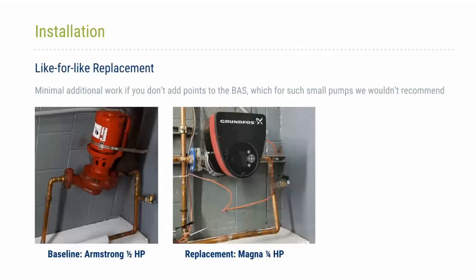Starting off with the installation of these pumps, right away it's a very simple installation. It's a like-for-like replacement. The pumps come with the necessary flange kits, so you pretty much remove the existing pump, and the new pumps will integrate right into the existing system, assuming you've met all your sizing constraints. Within both of our applications, we were able to use the existing BAS controls, which in this case was just the on-off signal coming from the BAS.